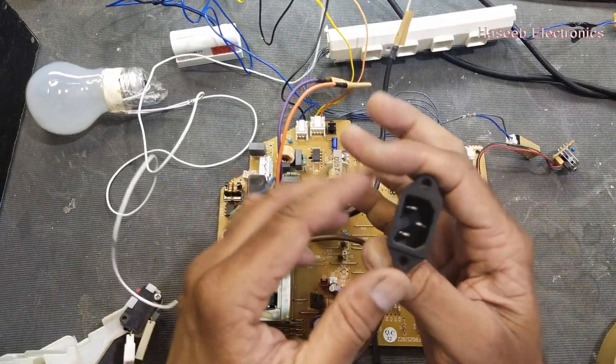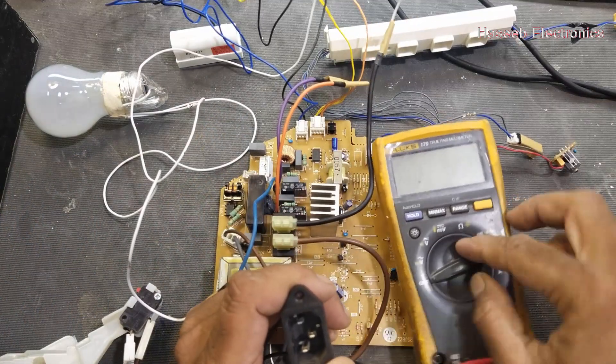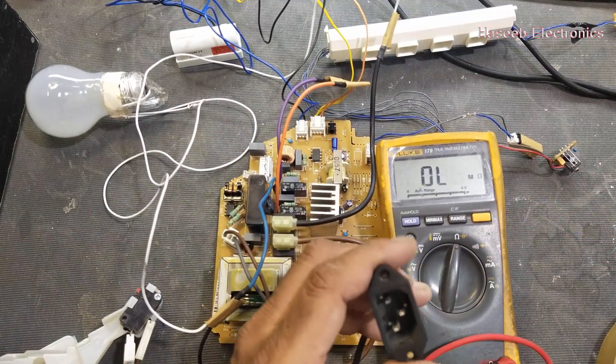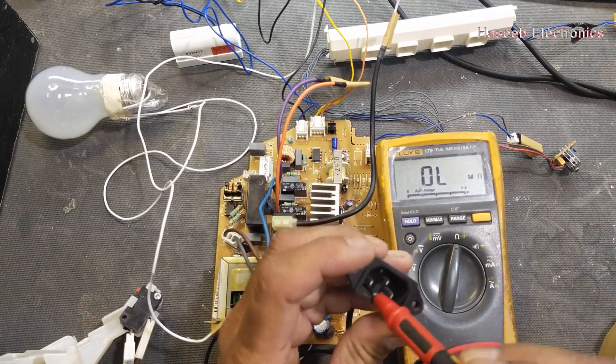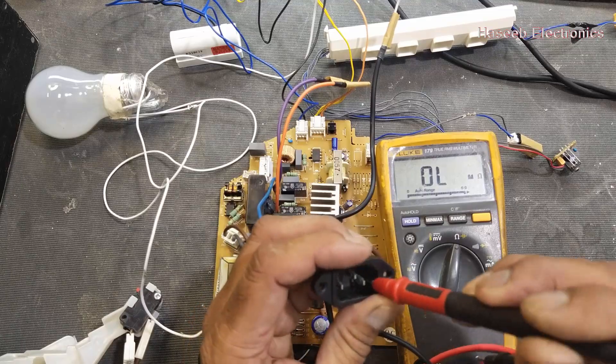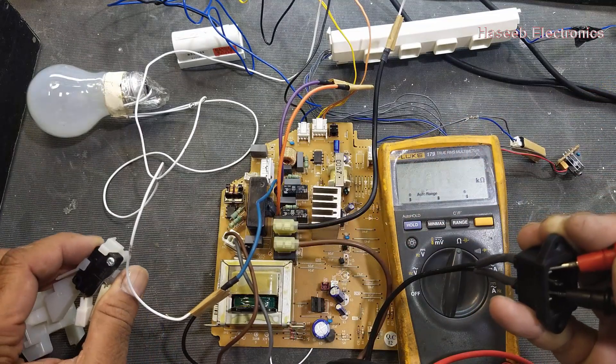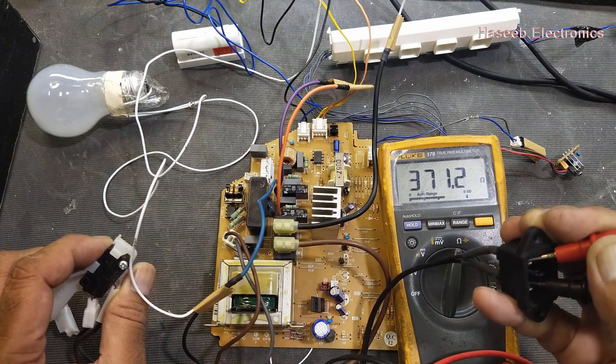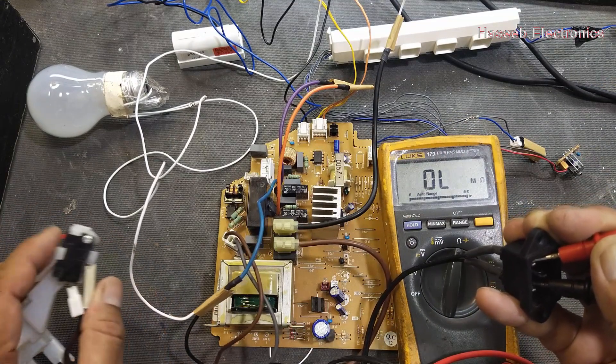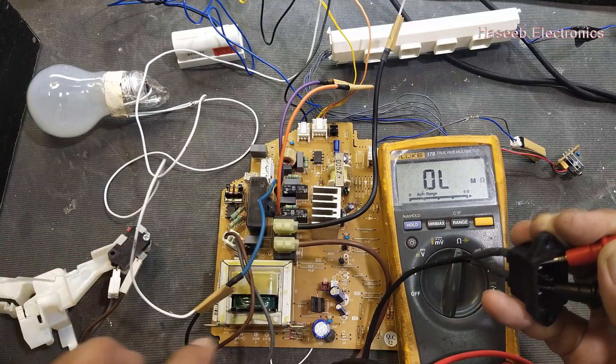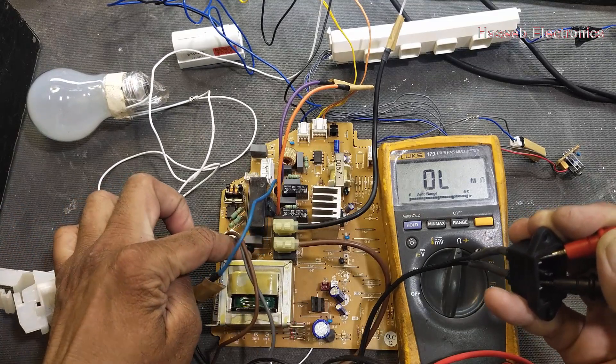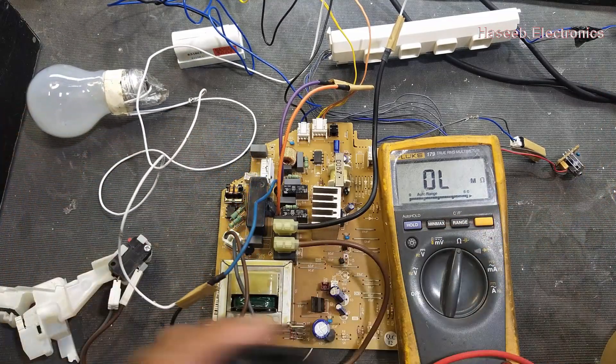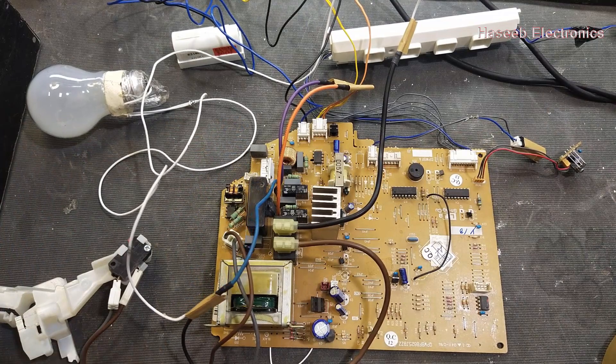The circuit for the transformer. Set multimeter to ohms, connect between the two line and neutral, and press this switch. The multimeter will show 371 ohms. Open this switch, so that means this switch is working, the transformer is good, the fuse is good, and our neutral and phase all connections are good now.